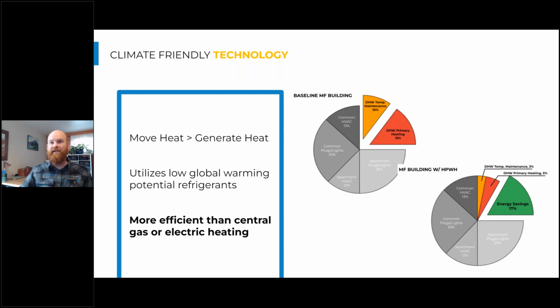And so we can see that these two pieces of the pie, the domestic hot water primary heating load, is reduced from about 15% to 5%. So cutting that by a factor of 3. And then domestic hot water temperature maintenance. This is our hot water circulation system, or the system that's keeping the water at temperature in the large distribution network of hot water piping.